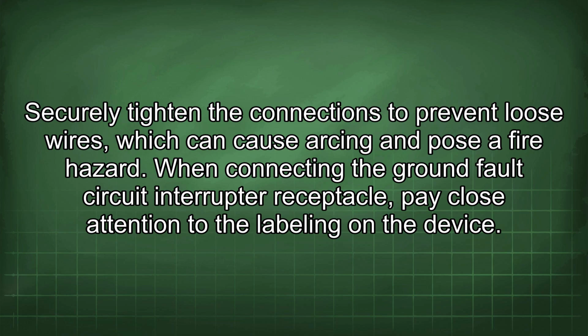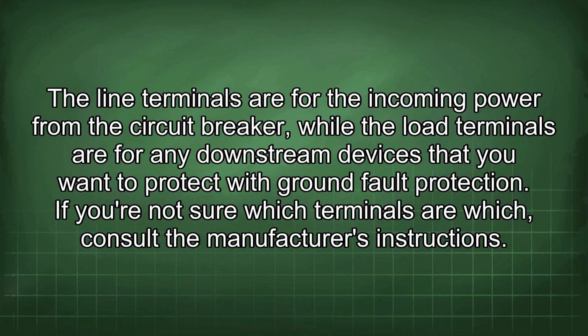When connecting the ground fault circuit interrupter receptacle, pay close attention to the labeling on the device. The line terminals are for the incoming power from the circuit breaker, while the load terminals are for any downstream devices that you want to protect with ground fault protection. If you're not sure which terminals are which, consult the manufacturer's instructions.